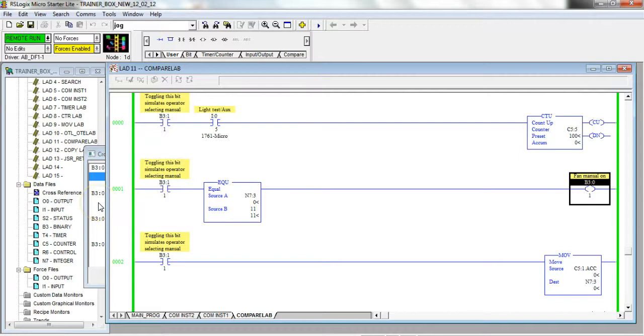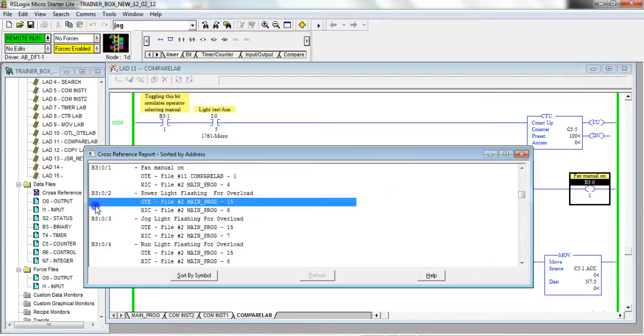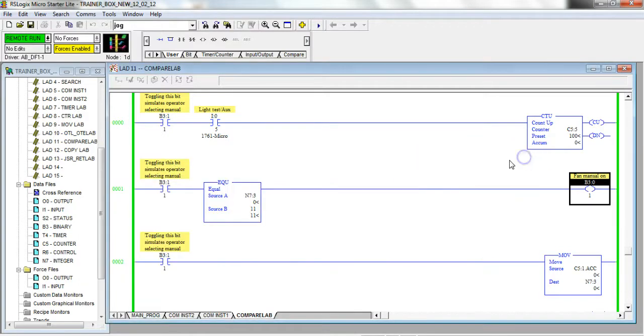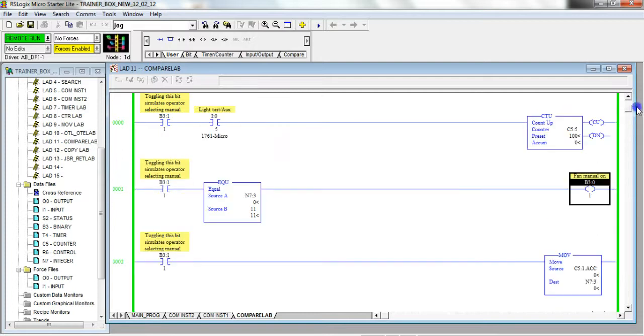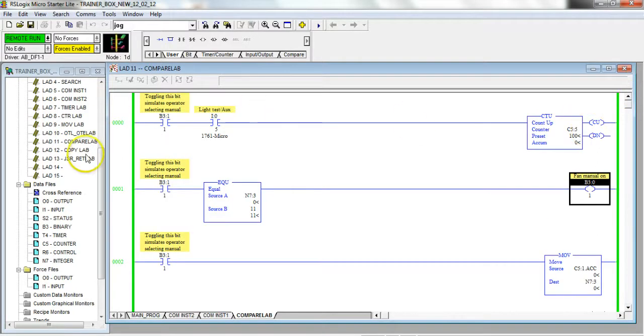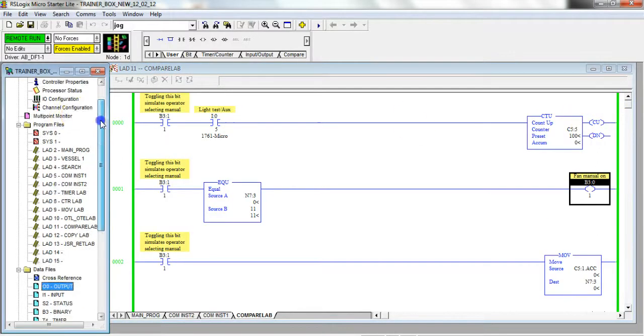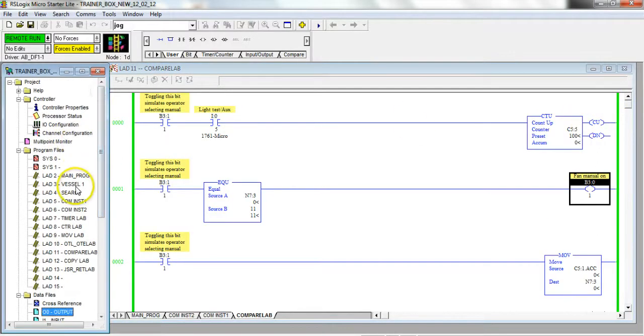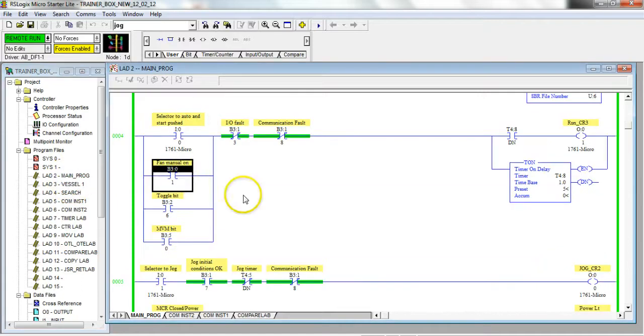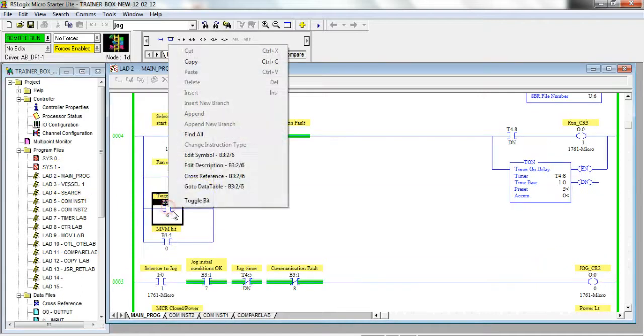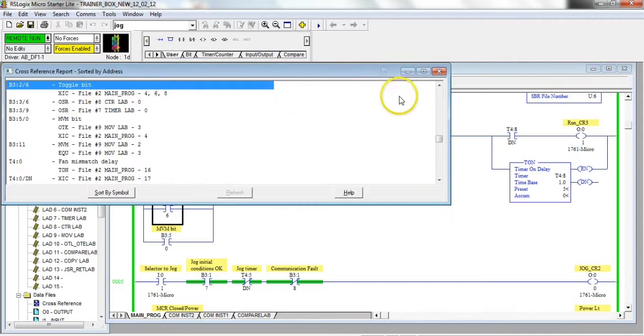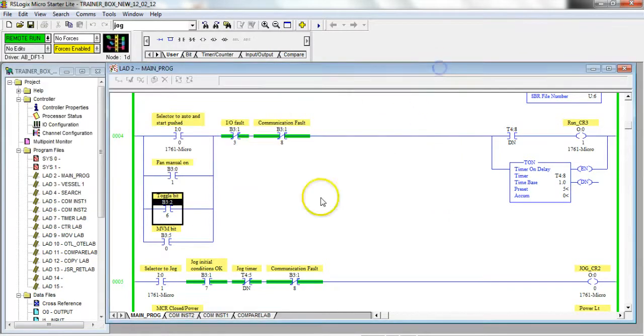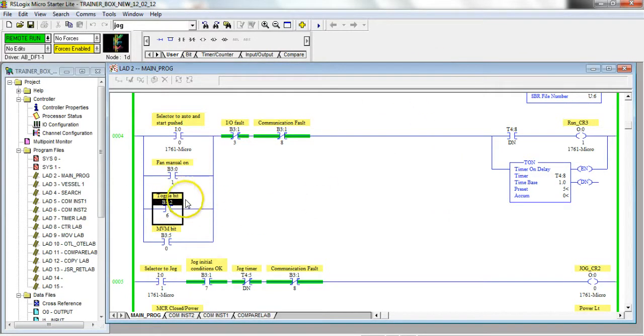So those are two different situations. If you're trying to toggle something and it won't let you do it, chances are it's being controlled somewhere else - it's being written to. That first toggle bit, if I go back and I do a cross reference of it, you'll see there is no OTE that's controlling it.